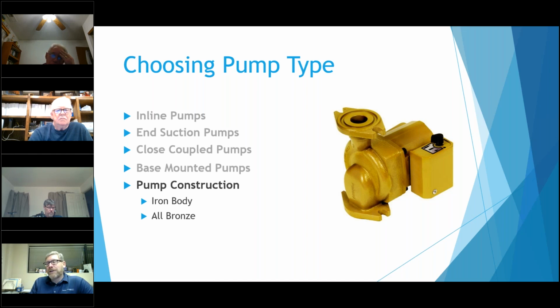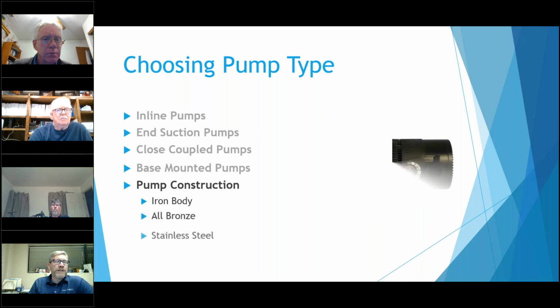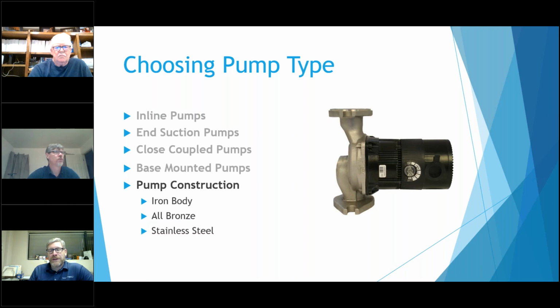So you definitely don't want to use iron body pumps on hot water recirc loops. I see quite a bit of them, so you want to make sure they are using bronze on those. It's a lot more expensive, in some cases double the price of the pump, but it's sure going to last a lot longer. The other material they're using for hot water recirc loops now is stainless steel body pumps. As the price of stainless steel has come down, and it's a lot easier to cast, it's become more prevalent to use it.